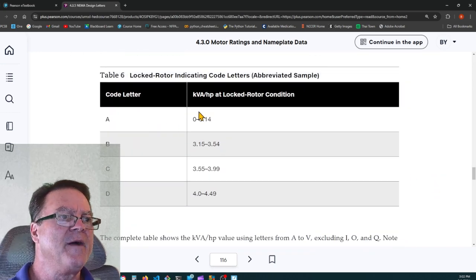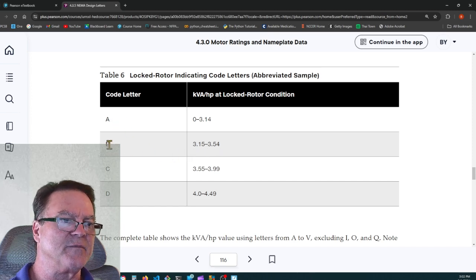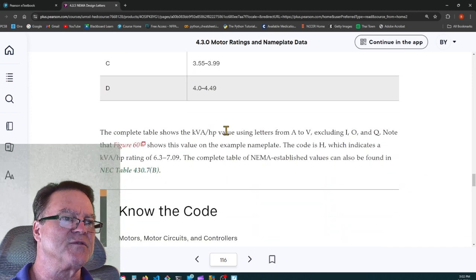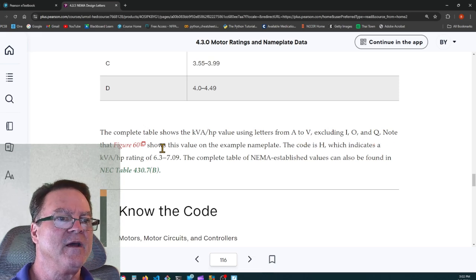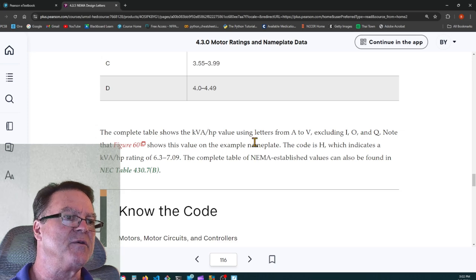So you can take the KVA of the motor divided by the horsepower. And 0 to 3.14 is code letter A, 3.15 to 3.54 is letter B, 3.55 to 3.99 is C, and 4.0 to 4.49 is D. The complete table shows the KVA per horsepower value using letters from A to V, excluding I, O, and Q. Figure 60 shows this value on the example nameplate. All right.